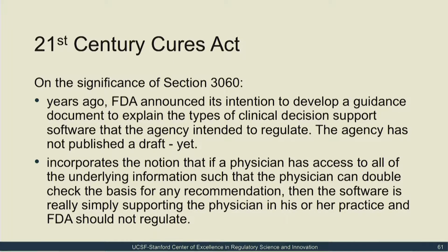The Act does not, of course, replace the need for a guidance, but it does bring light into one especially important concept: if a physician has access to all of the underlying information such that the physician can double-check the basis for any recommendation, then the software is really simply supporting the physician's practice of medicine, and the FDA should not regulate. It's worth emphasizing that the Act amended the medical device definition, which has happened very infrequently, generally only once every several years, since the medical device amendments of 1976.